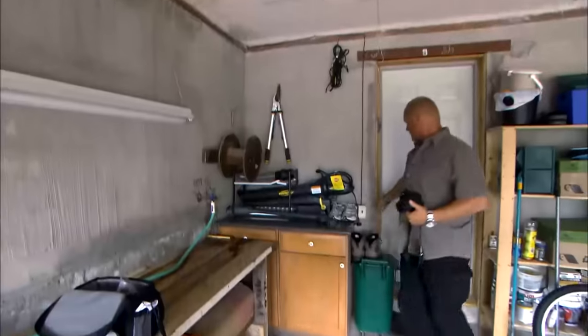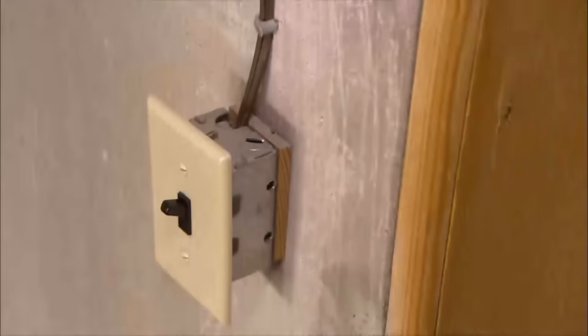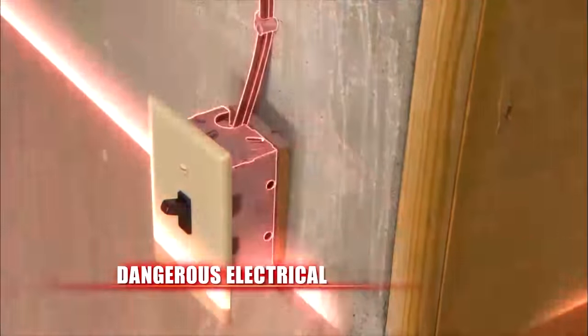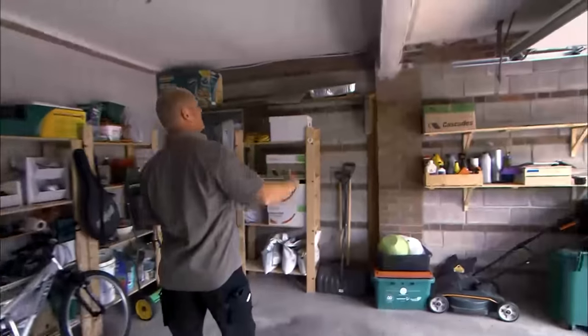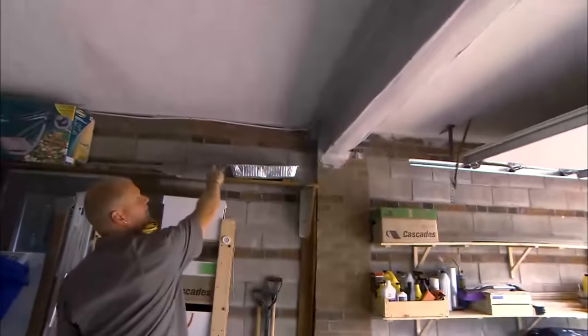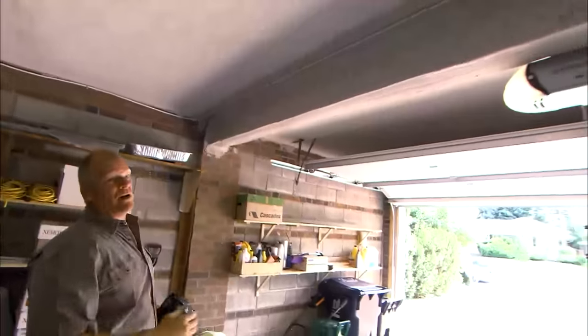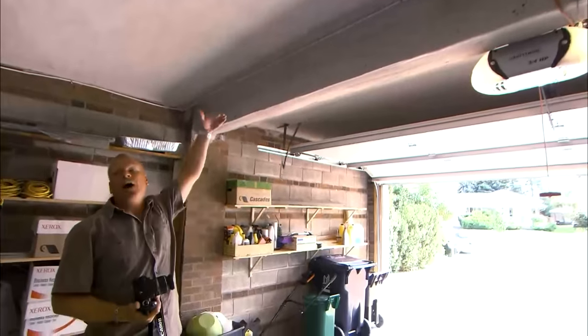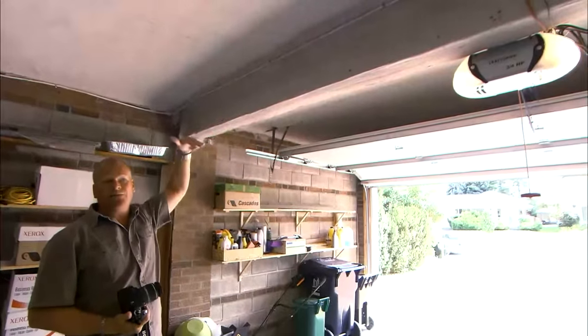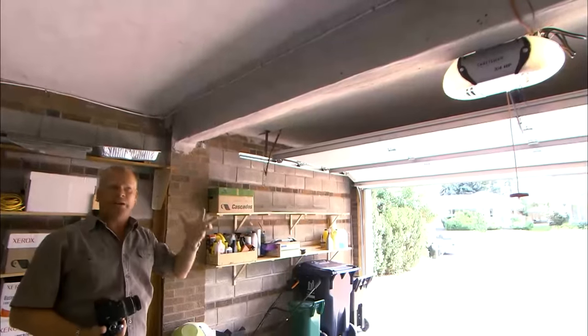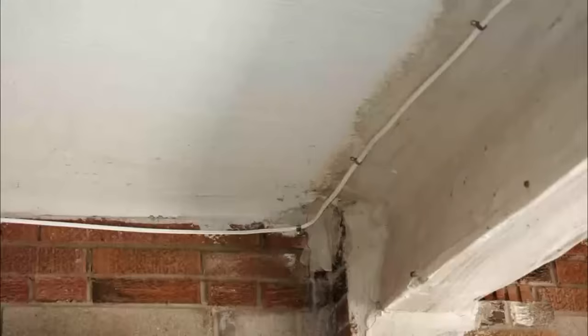The extension cord comes down to the switch, totally against code, which I did not read in the report. Other things we don't do is take a Romex line like this and just clip it on around, especially inside the garage. The pro about this is it's up high, you can't hit it, and as long as it's at a certain height, it should be a BX or an armored cable, just for safety purposes.